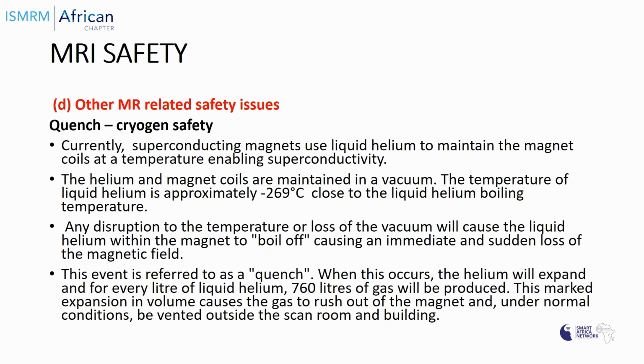Now, quench or cryogen safety is another MRI-related safety issue that needs to be considered. Currently, superconducting magnets use liquid helium to maintain the magnet coils at a temperature enabling superconductivity. The helium and magnet coils are maintained in a vacuum. The temperature of the liquid helium is approximately minus 269 degrees Celsius, close to the liquid helium boiling temperature.